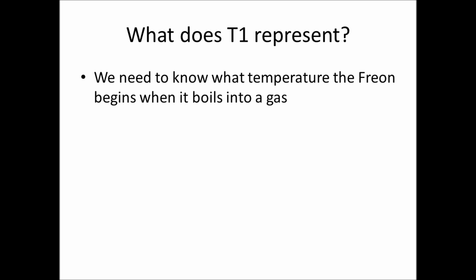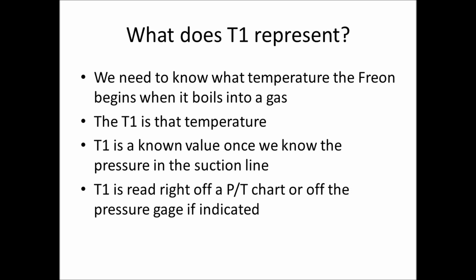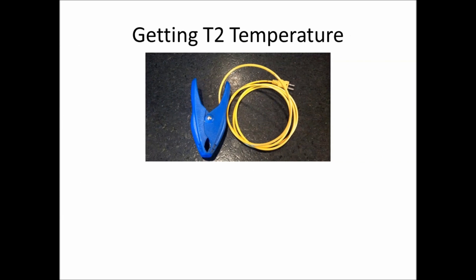What does T1 represent? We need to know the temperature of the freon before it boils into a gas — that is the T1 temperature. T1 is a known value once we know the pressure in the suction line, and it's read right off a pressure-temperature chart or off the pressure gauge as indicated.